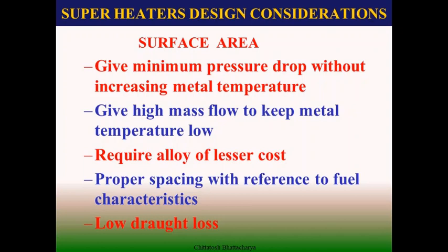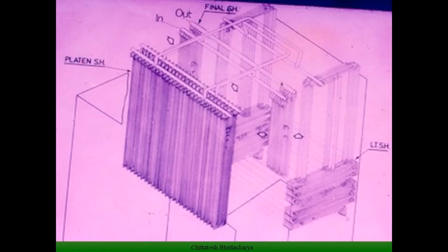That means a constant temperature difference is maintained as we increase the steam temperature, and heat absorption is kept at a constant rate. Beside that, the superheaters absorb heat in such a way that as a result of heat absorption, the flue gas temperature is reducing. Due to the reduction of flue gas temperature, the volumetric flow is also reduced, so velocity is also controlled by heat absorption.